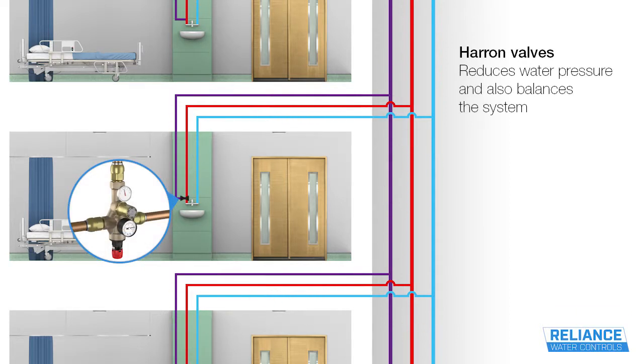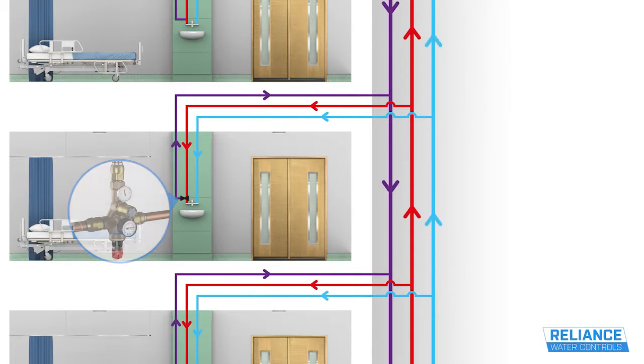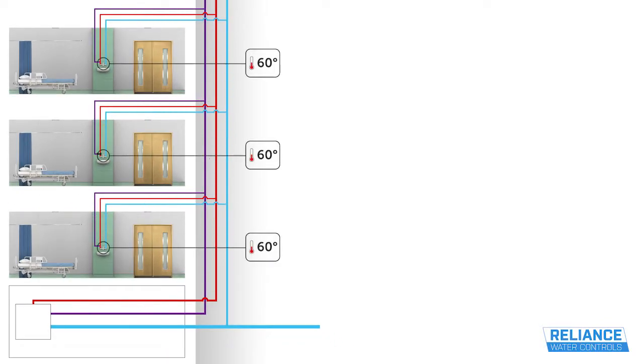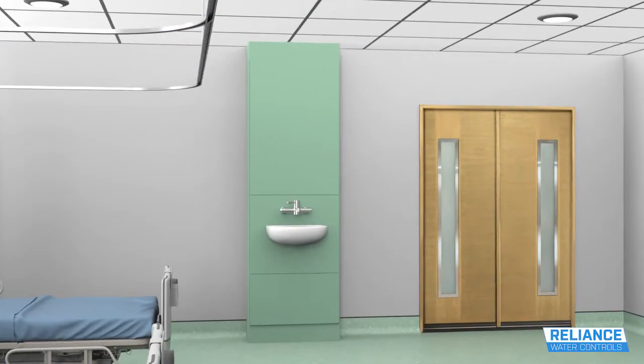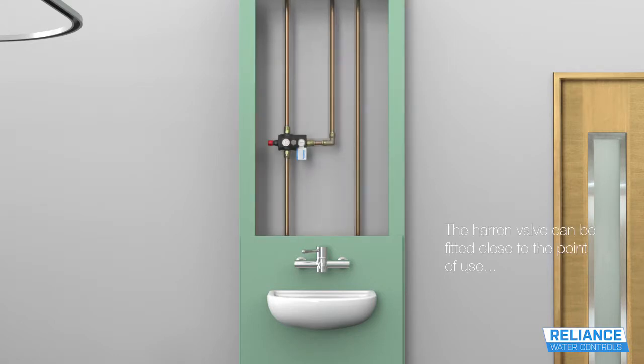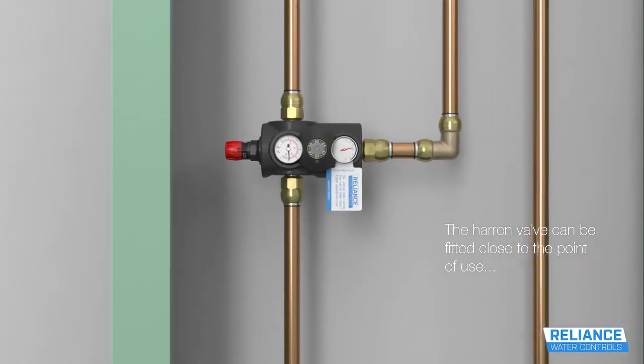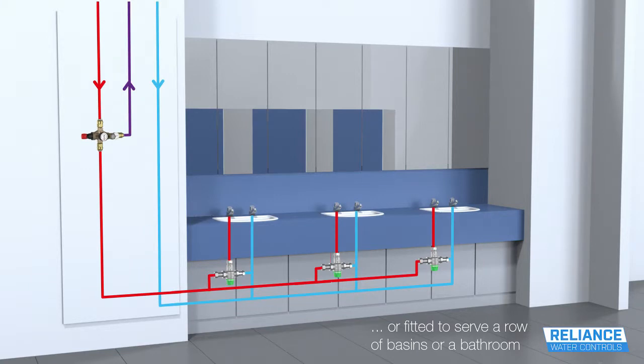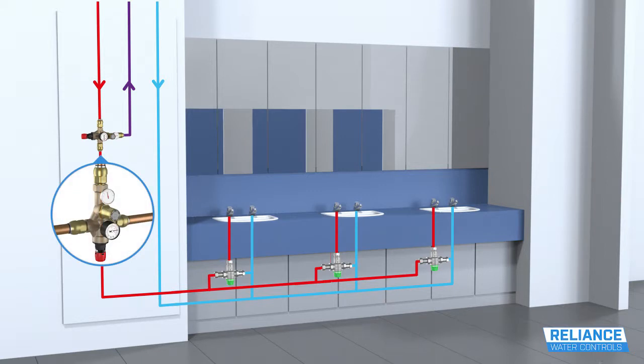Harron Valves, however, both reduce water pressure and balance the system by regulating the flow within it depending on temperature. A Harron Valve can be installed to serve an individual outlet or to control a group of terminal fittings fed from a branch. It is suggested that the valve should always be positioned on the return line close to the point of use, so that the dead leg of uncirculated hot water is kept to a minimum.